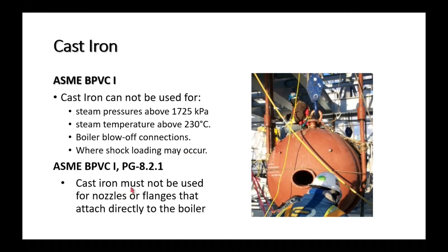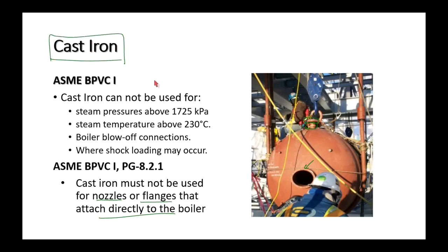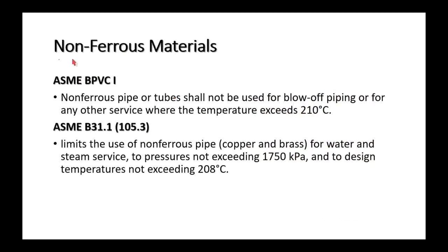Cast iron also cannot be used for nozzles or flanges that attach directly to the boiler. In our field, we don't see cast iron on high-pressure steam boilers — except occasionally on low water cutoffs or water columns. For non-ferrous materials: ASME BPVC Section I says pipes or tubes that are non-ferrous shall not be used for blow-off piping or any service where temperature exceeds 210°C.